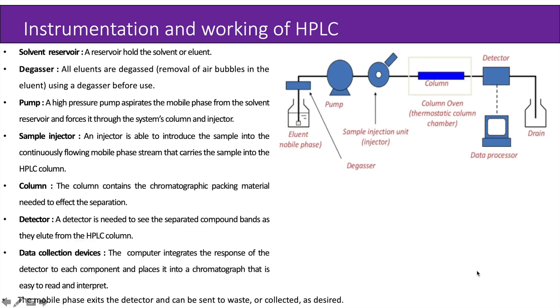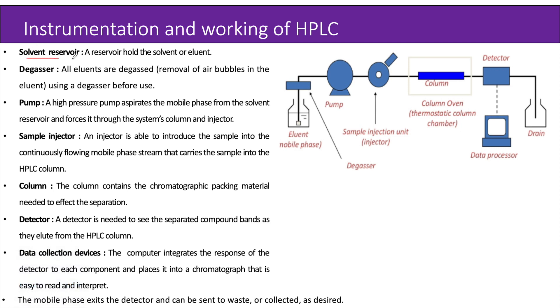Now let us see the instrumentation for HPLC. First is the solvent reservoir, where a reservoir holds the solvent or eluent. Second is the degasser — all eluents are degassed, that is, air bubbles are removed from the eluent using a degasser before use. Third is the pump — a high pressure pump aspirates the mobile phase from the solvent reservoir and forces it through the system's column and injector.